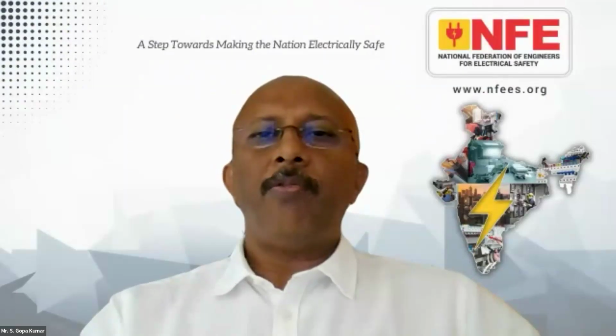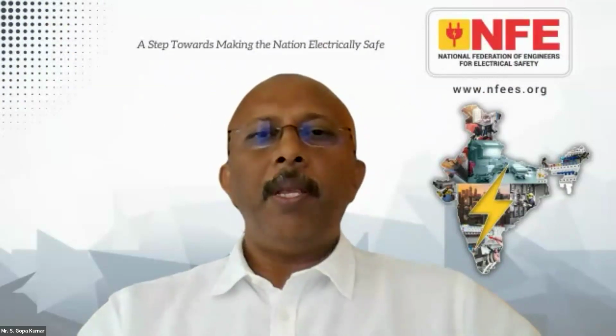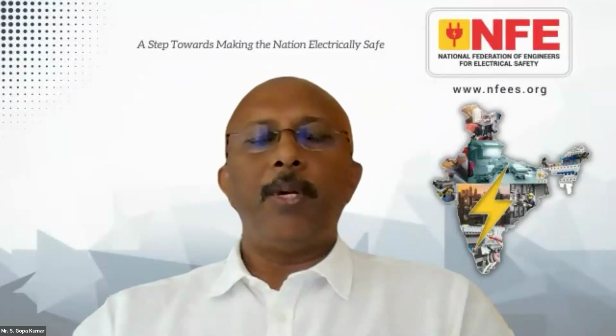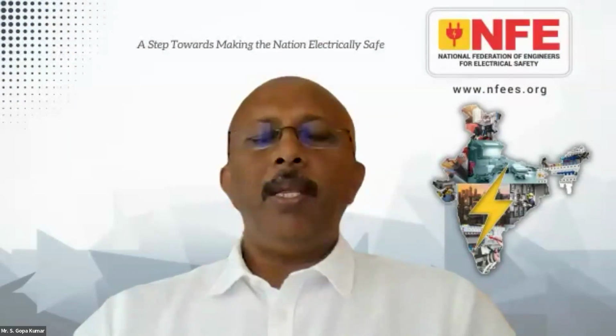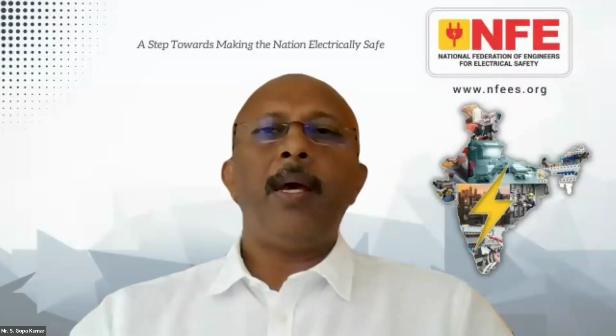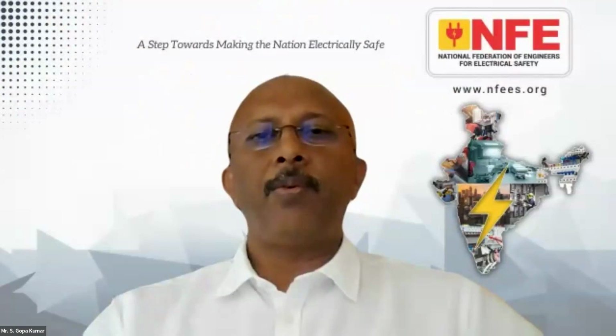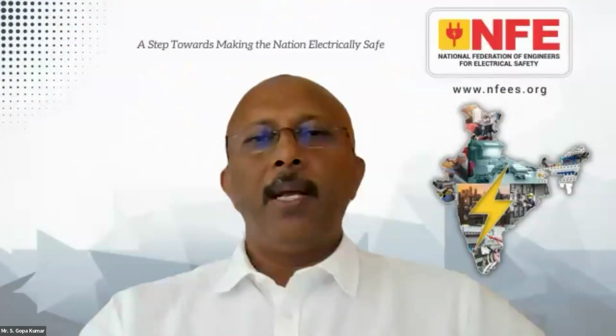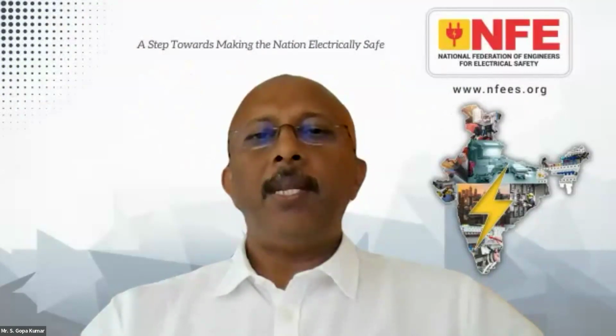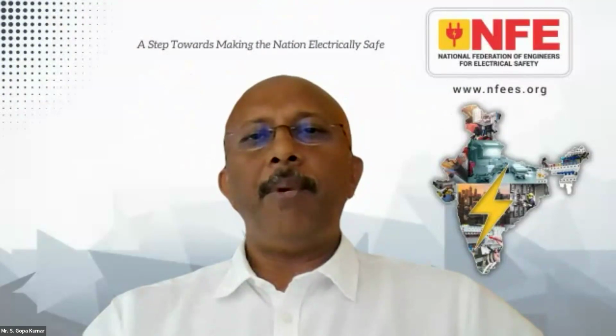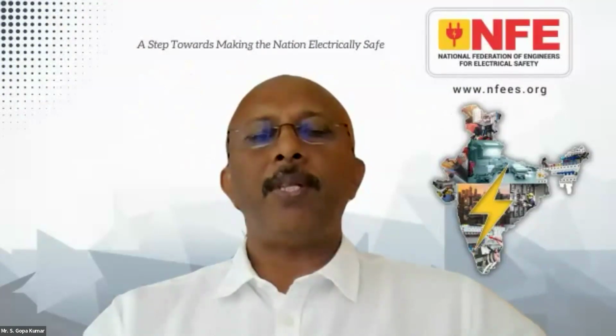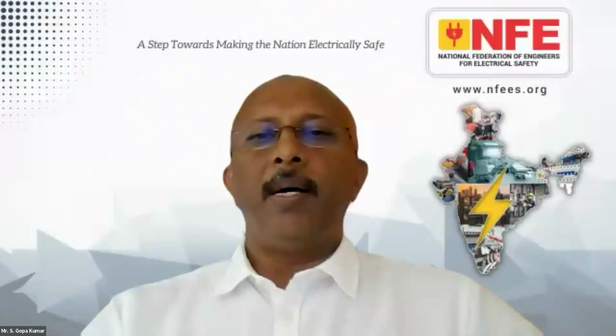Mr. Niranjan also asked about the role of supplementary equipotential bonding in electrical safety for medical equipment and medical electrical installations. Supplementary equipotential bonding means in Group 1 and Group 2 medical locations, that is critical areas, all dead metal parts must be interconnected so that the patient or people working there don't get shock from energies produced by the equipment. We interconnect the different metal parts, and this interconnection shall be tested with a meter of 10 amperes or 25 amperes, and it should show a resistance of less than 100 milliohm. That is the technical requirement, Mr. Niranjan.